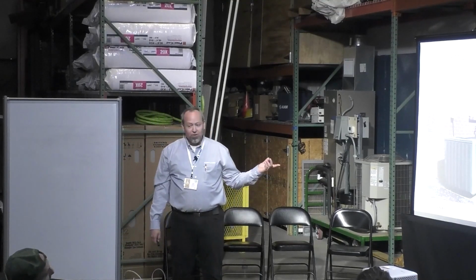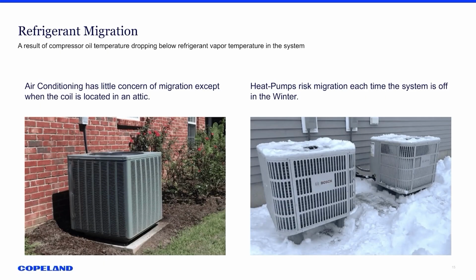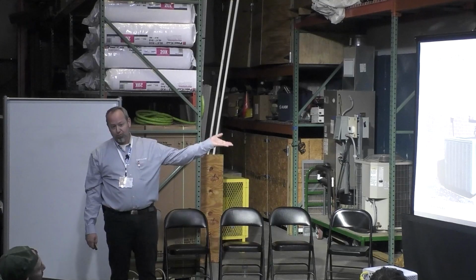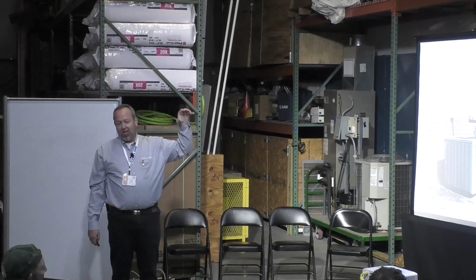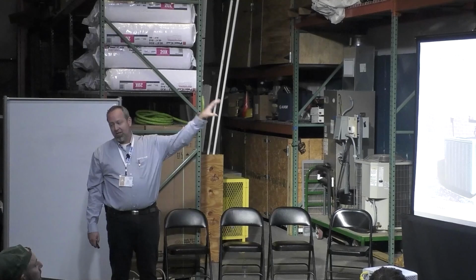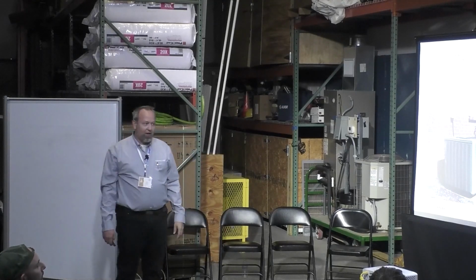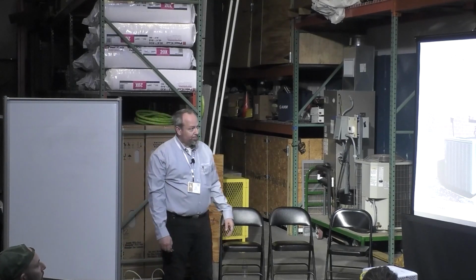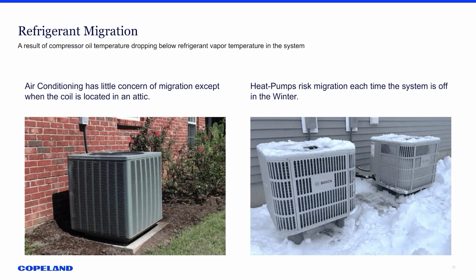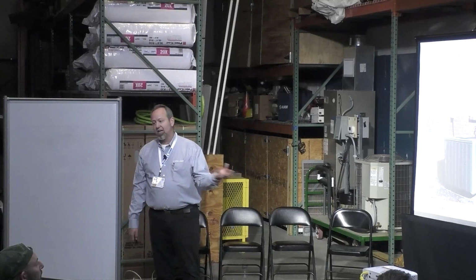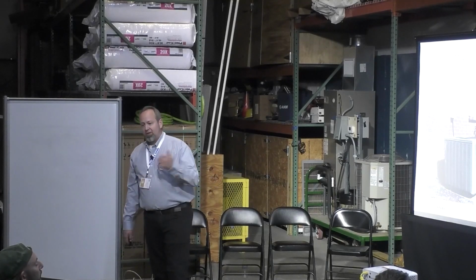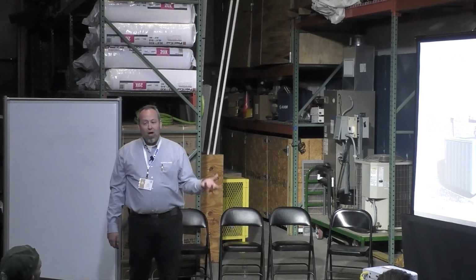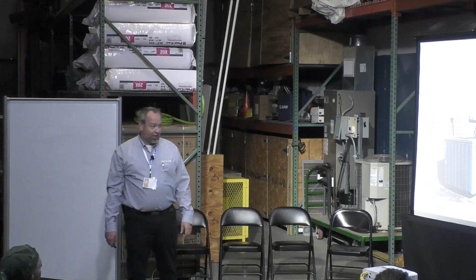So is it a concern? No. If you're in an attic, if you're in a basement, it's not a problem. If you're in an attic where it's 100+ degrees in the summertime for the AC, and it's hotter up there than it is outside, then yeah, you need a crankcase heater on a straight AC. It's the heat pumps that are the risk, especially when they're off in the wintertime when it's colder outside than inside, where that liquid's going to build up outside in that condenser and compressor.